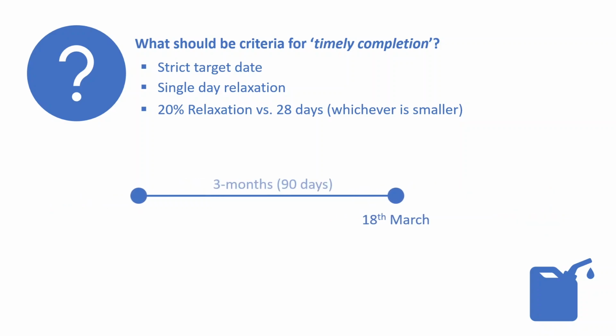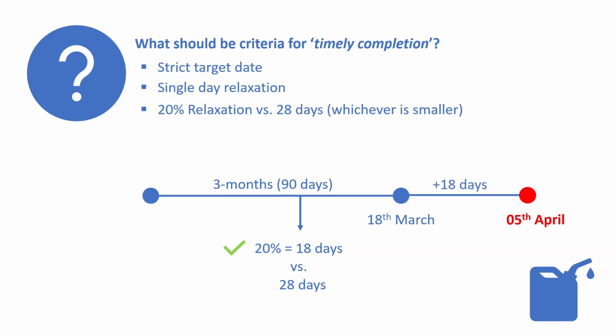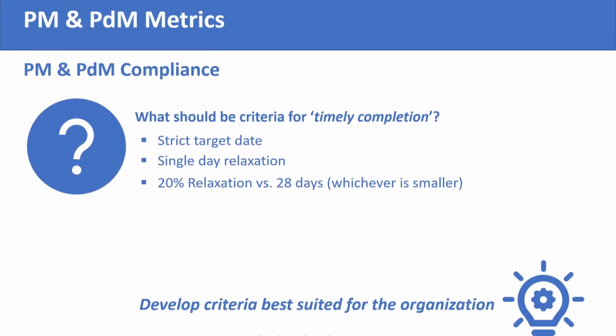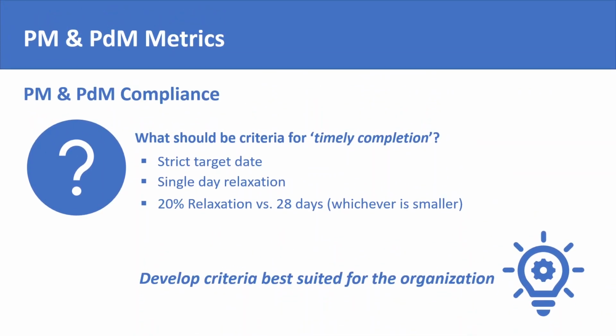If let's say the manufacturer had recommended oil change every 3 months, which is 90 days, then 20% relaxation would have been 18 days. Since it is not larger than 28 days, we would have used an 18 days relaxation. It means we would have considered oil change to be completed timely even if the target date was passed by 18 days. Every maintenance organization should develop criteria best suited to their systems and site conditions before using this metric.